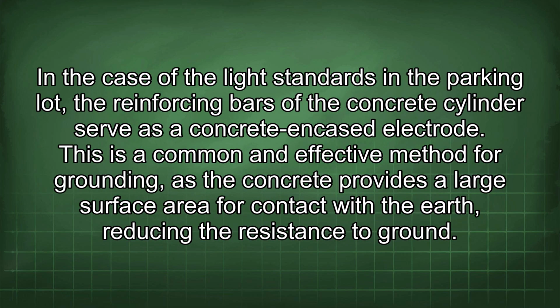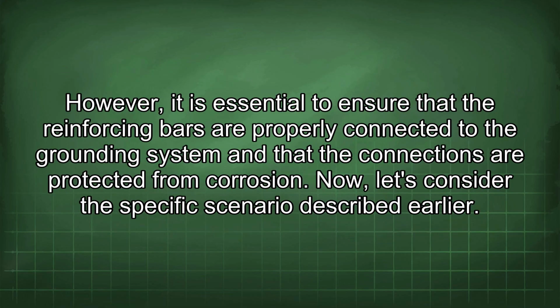In the case of the light standards in the parking lot, the reinforcing bars of the concrete cylinder serve as a concrete encased electrode. This is a common and effective method for grounding, as the concrete provides a large surface area for contact with the earth, reducing the resistance to ground. However, it is essential to ensure that the reinforcing bars are properly connected to the grounding system and that the connections are protected from corrosion.